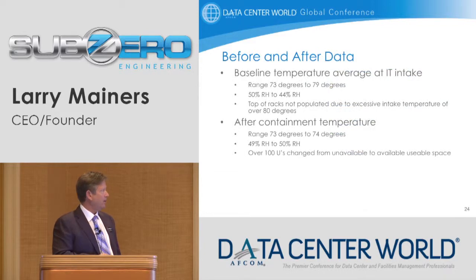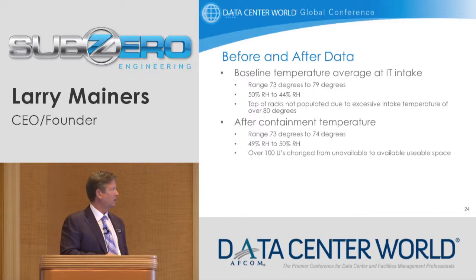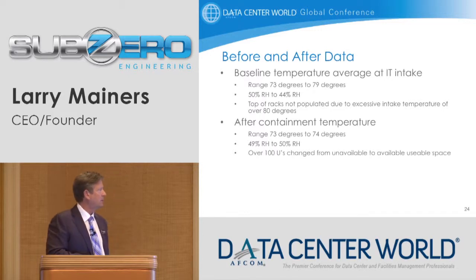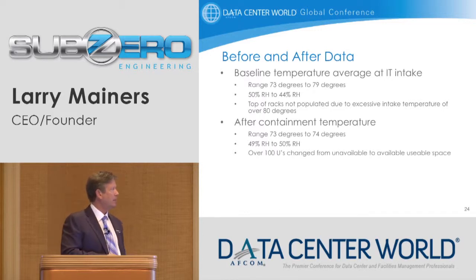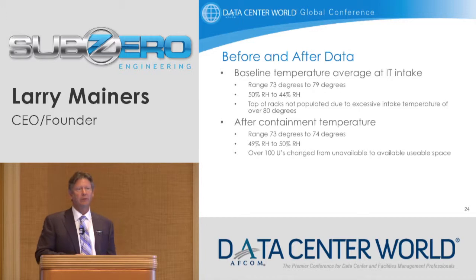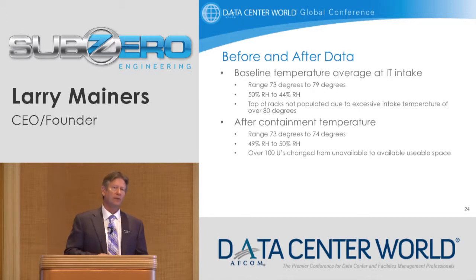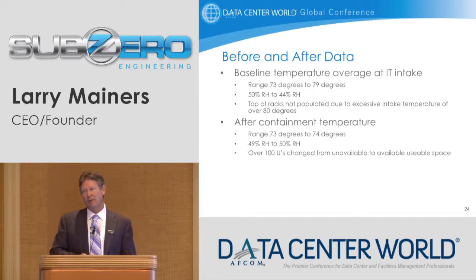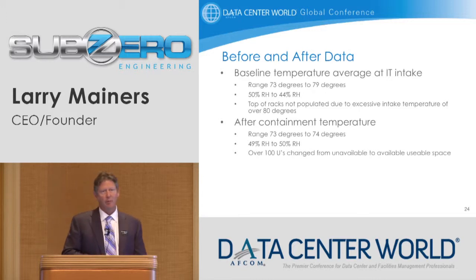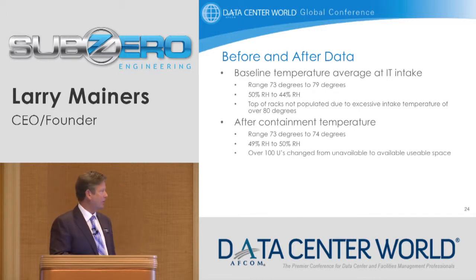We can see here the temperature and relative humidity changes that took place, and the ability to actually add racks, because the company policy prior to this airflow management was that the top U's were not fully populated. That's another value of airflow management: the ability to fully populate the rack. So there are your after numbers and the changes in thermal load relative to usable space.